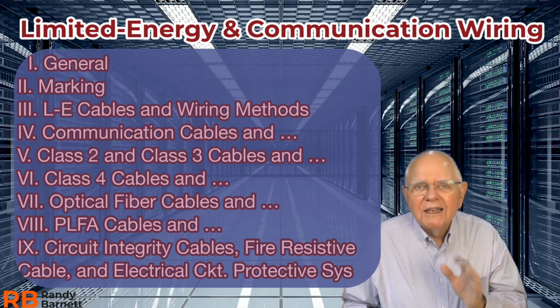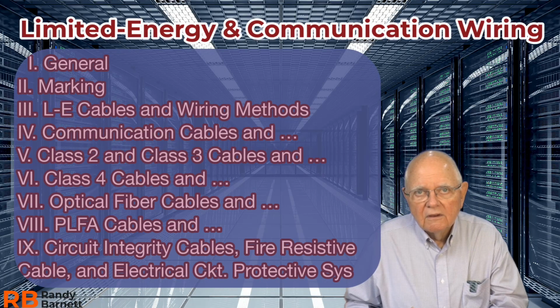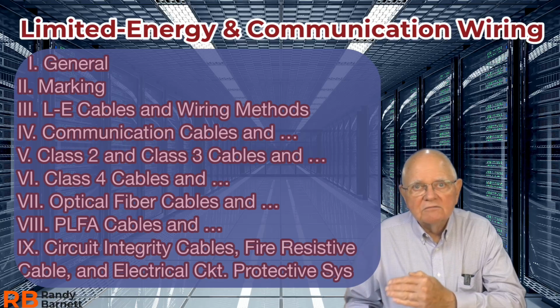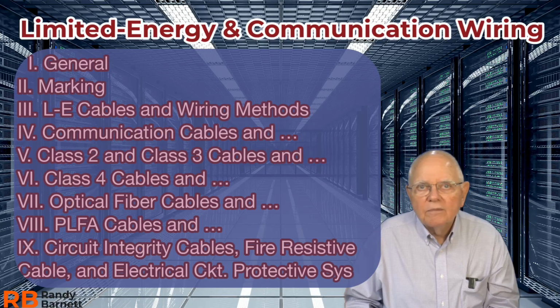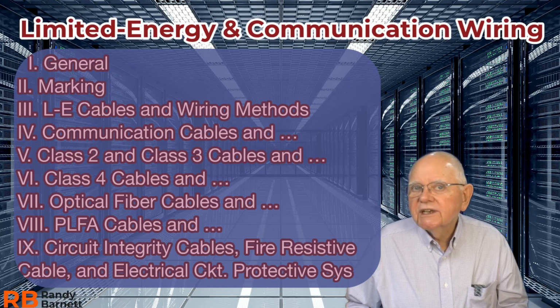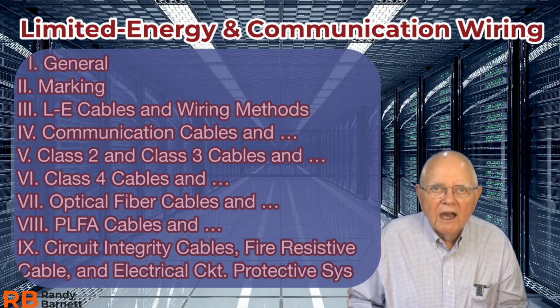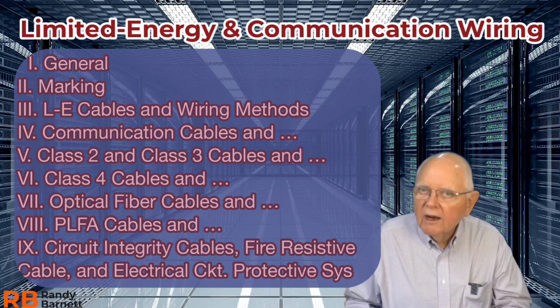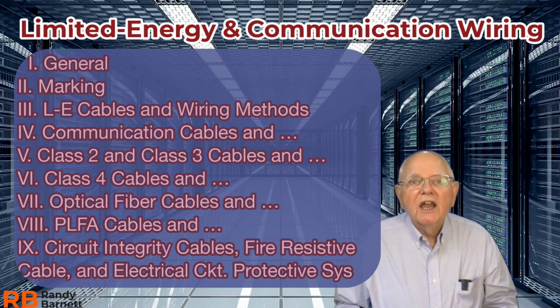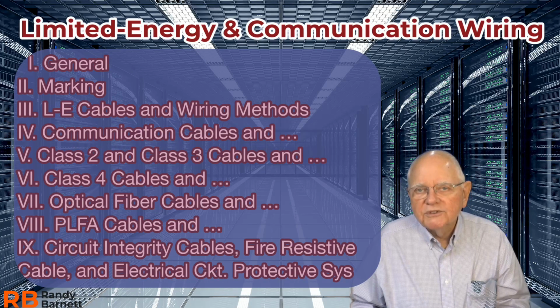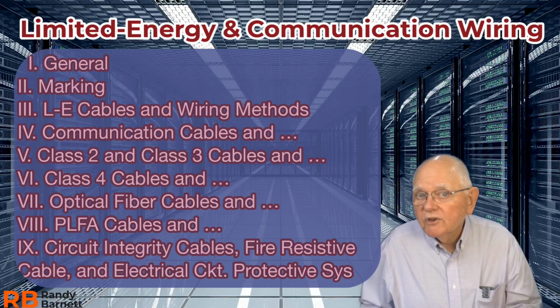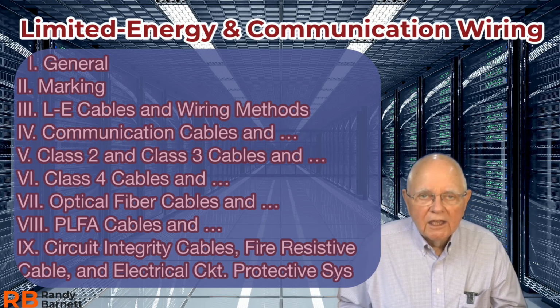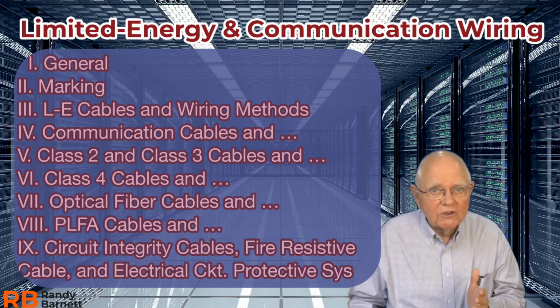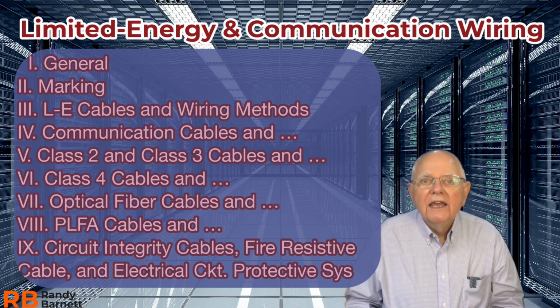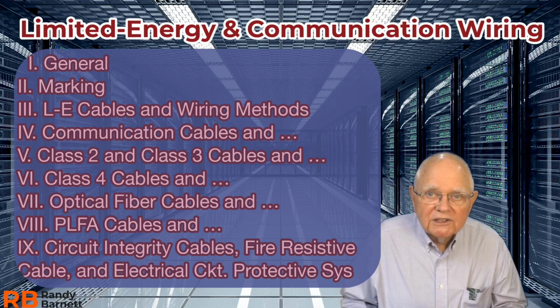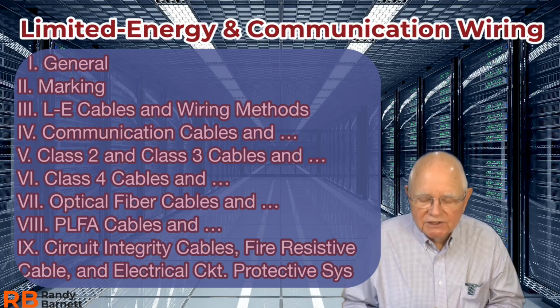Part 3 is for limited energy cables and wiring methods. So remember the wiring method. Am I going to use conduit? Do I need conduit? What types? So on and so forth. Part 4, communication cables and wiring methods. Part 5, Class 2 and Class 3 cables and wiring methods. Part 6 is Class 4, fault mitigated cables and wiring methods. Part 7 is for our optical fiber cables. Part 8 is for our power limited fire alarm cables. And Part 9 is for circuit integrity cables, fire resistive cables, and electrical circuit protective systems.